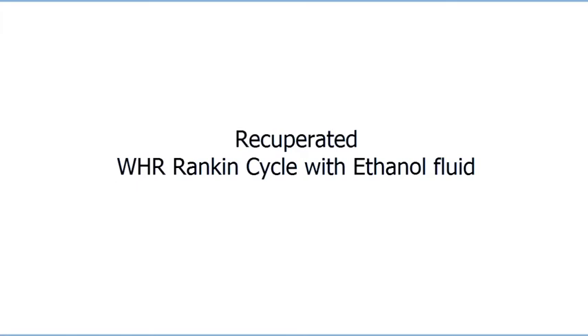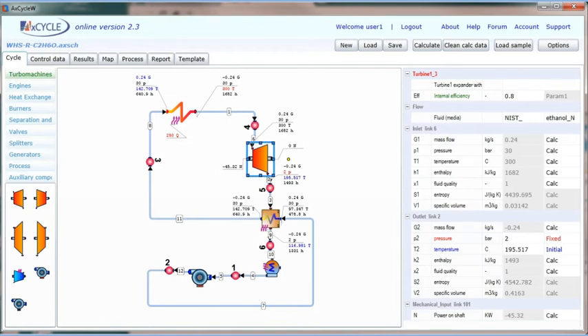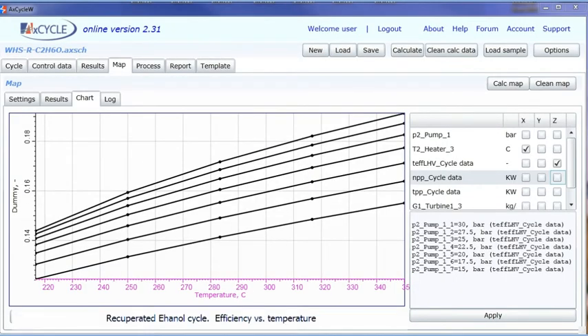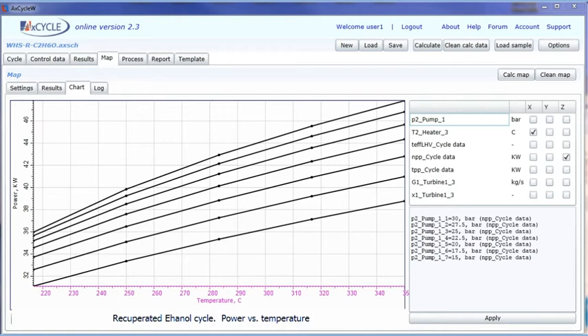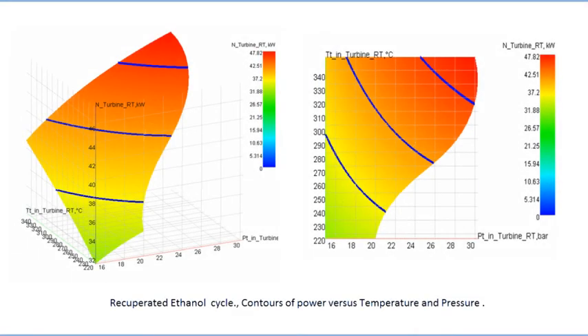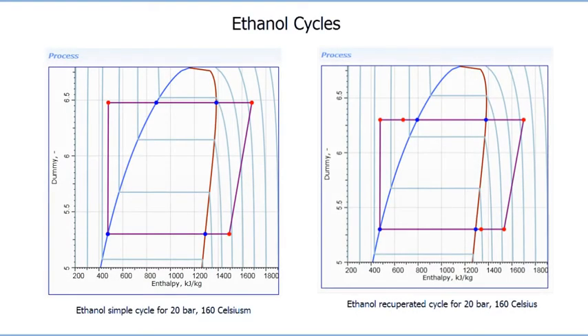The recuperated waste heat recovery Rankine cycle with ethanol as working fluid is shown for an operation point of 30 bar, 300 Celsius. The output flow after the turbine is about 195 Celsius, allowing use of a recuperator to heat the liquid after the pump from 97 up to 142 Celsius. The recuperated ethanol cycle power versus temperature and efficiency versus temperature plots are shown, along with contours of power versus temperature and pressure defining the operational range. The pressure-enthalpy diagram shows the amount of heat extracted before the condenser with the recuperator and used for preheating fluid at the heater inlet.